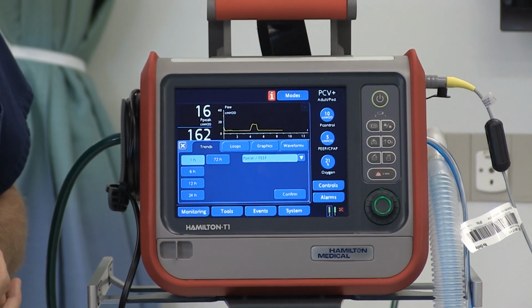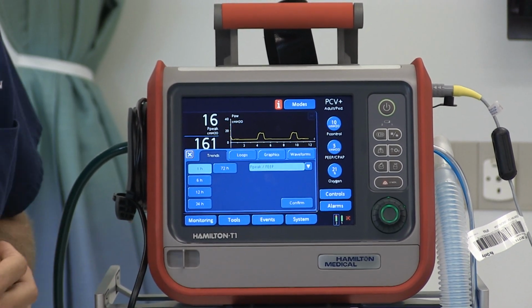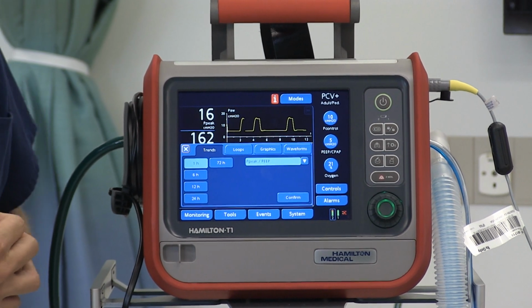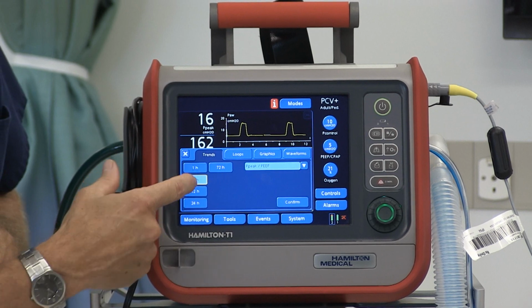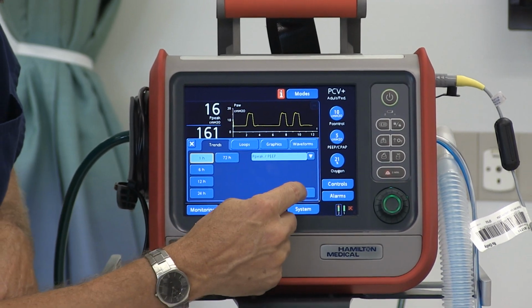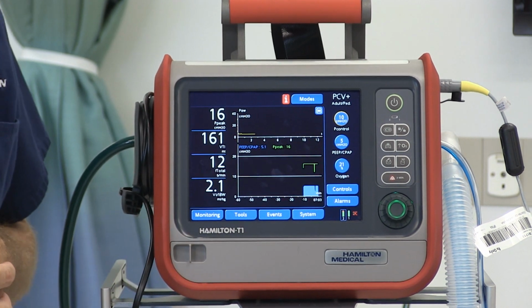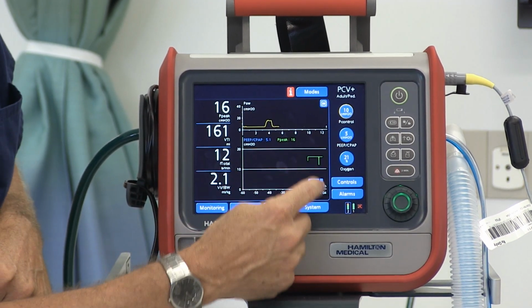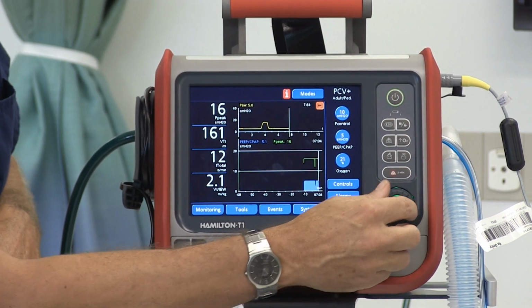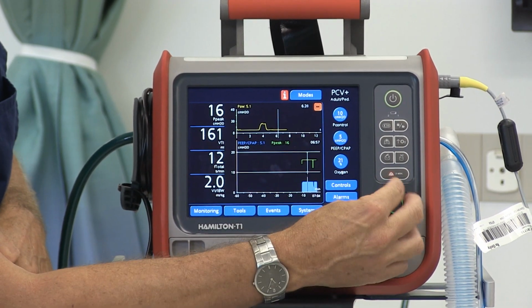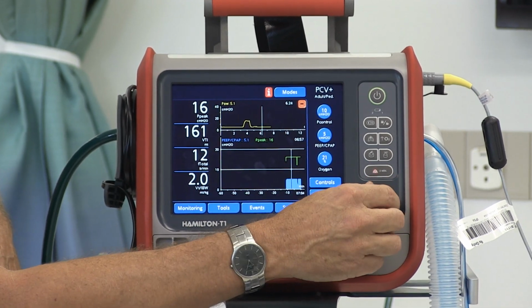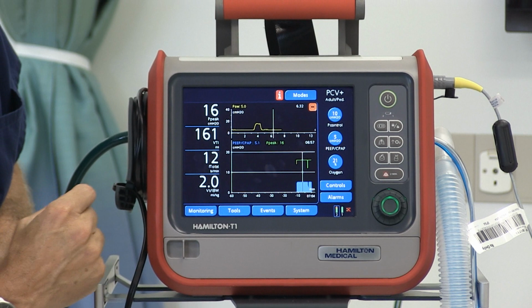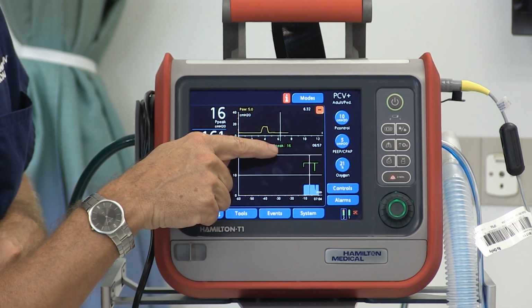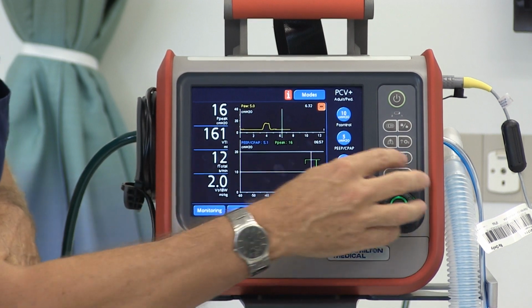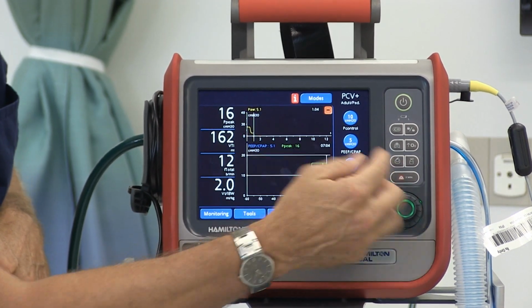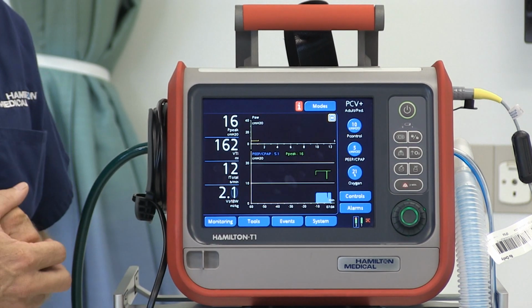Next tab over, trends. The ventilator will actually trend every monitored parameter for up to 72 hours. To display a trend, select the trend time. Let's just go with a 1 hour here, confirm, and we see the trend panel. To scroll back, to examine the trend, this is the screen freeze button. If I activate that, I can scroll back and examine the trends for the past hour. Wherever the cursor is pointing, the time is displayed here, and the pressure or whatever monitor parameter I'm looking at is displayed right there. And notice this button also freezes the waveforms, so I can examine a pressure or flow waveform if I'd like.